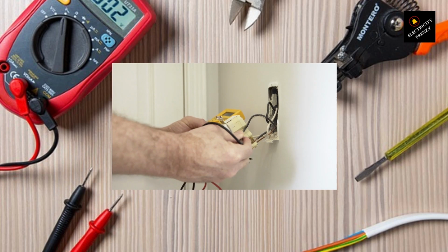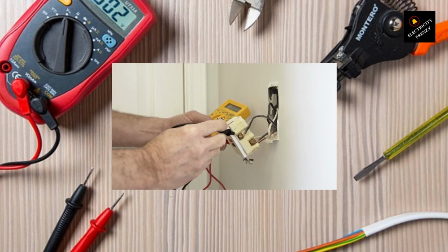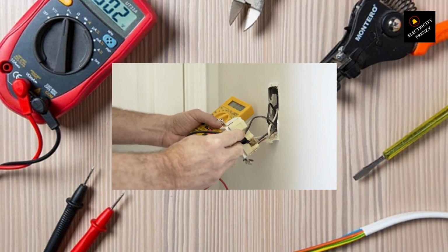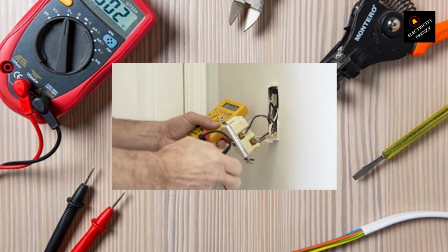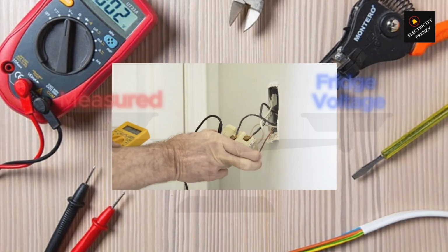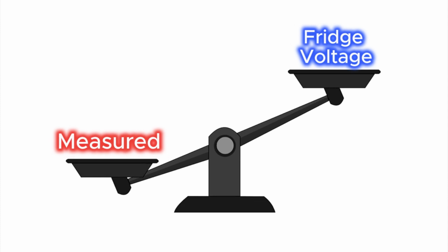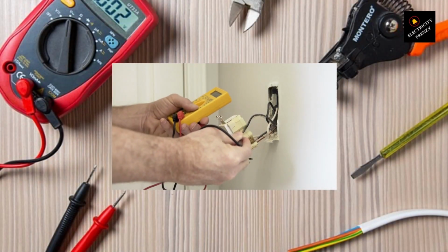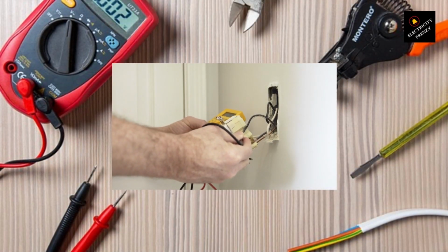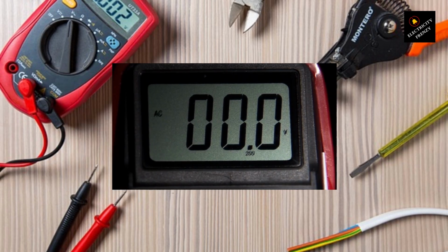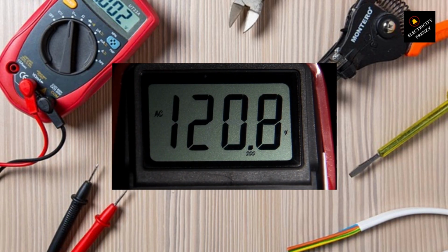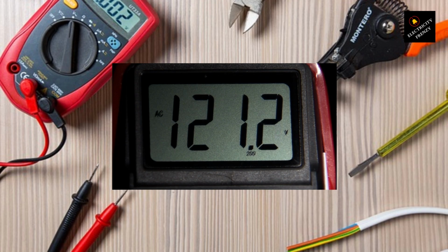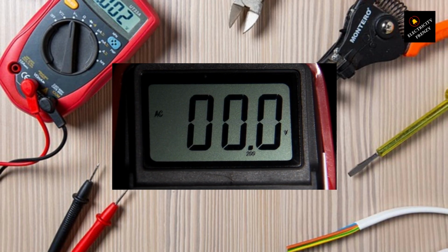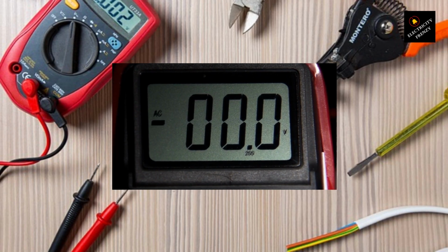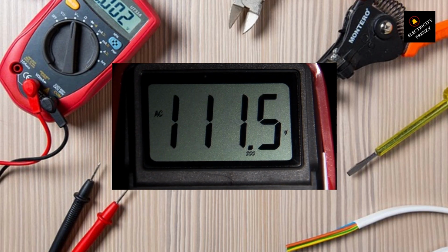Low voltage. To diagnose low voltage issues, measure the voltage at the outlet using a multimeter or contact a professional electrician to perform the measurement. Compare the measured voltage with the specified operating voltage range for the refrigerator, usually found in the user manual or on the manufacturer's website. If the measured voltage consistently falls below the specified range, contact the power utility company to address the low voltage issue or consult with an electrician to evaluate and potentially upgrade the electrical system.